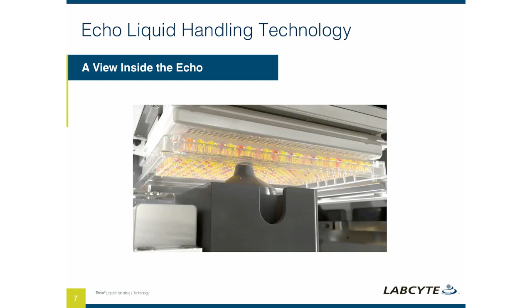So that plate is inverted, and it captures that droplet as it travels across the space between those plates. The plates, as I mentioned before, can be 384 well plates. They can be 1536 well plates. We can transfer from 384 into 1536, from 1536 into 384, all the different combinations there. So really one of the big benefits of the Echo instrument over a tip-based system is its ability to transfer from any well into any well.